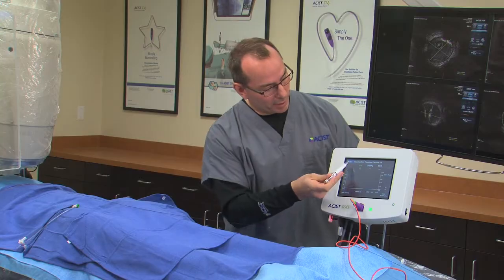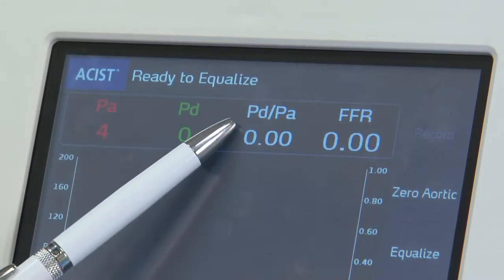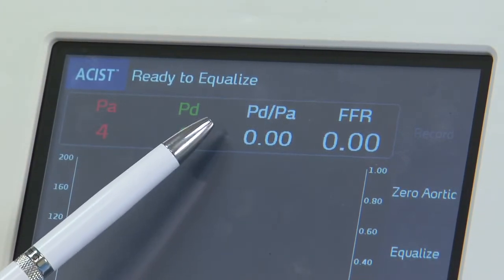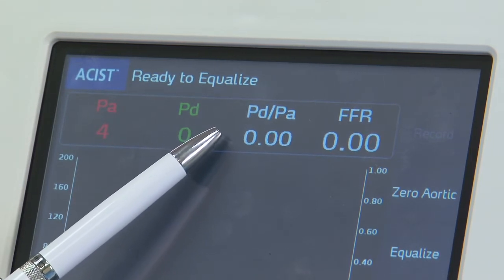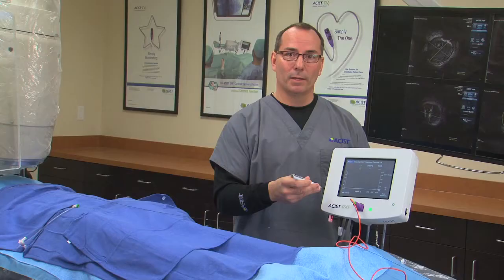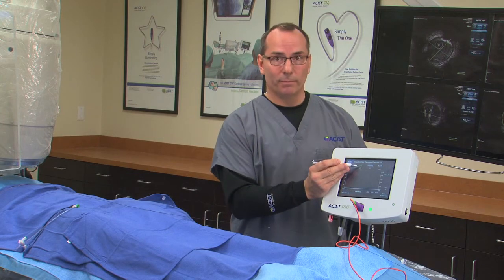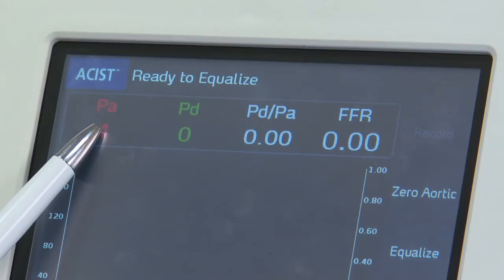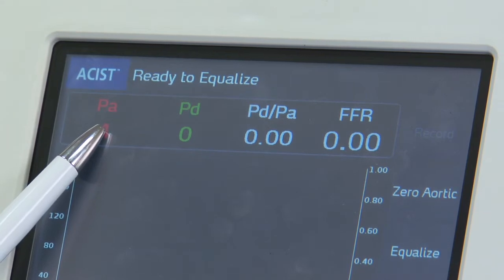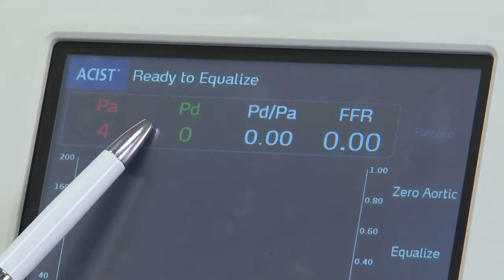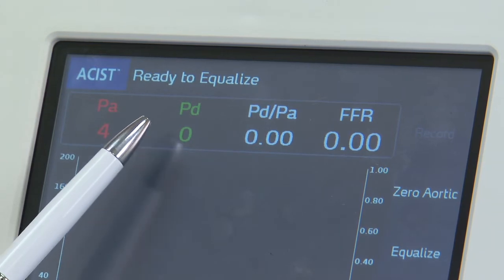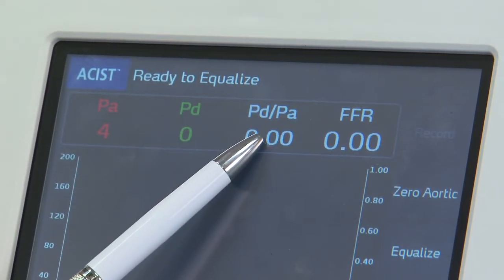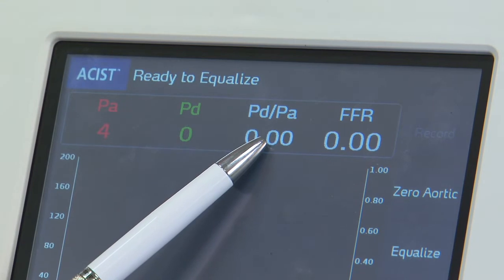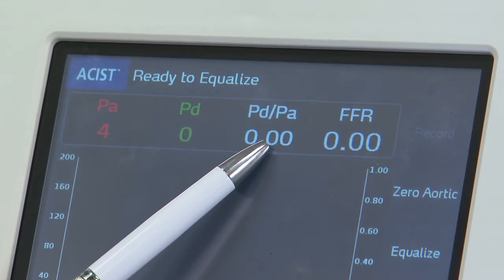Across the top of our system is the status bar, and it tells us exactly what step needs to be done next to move on into the FFR procedure. The PA value, this is the mean arterial pressure of the patient. The PD is the mean distal coronary pressure. The PD-PA ratio, often referred to as the resting gradient, is best utilized when equalizing pressures. When equalizing, the PD-PA ratio should be 1, meaning there's a 1-to-1 relationship between the pressures.